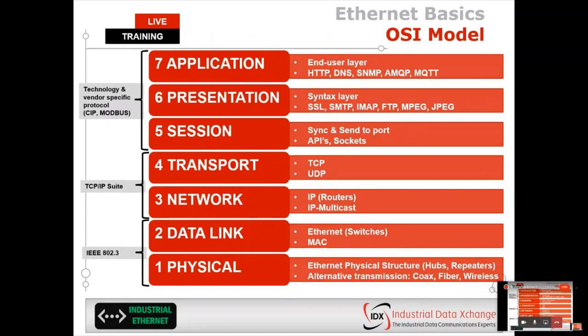This table in front of you is called an OSI model. An OSI model is used to describe a communication system - it can describe any communication system. For example, PROFIBUS doesn't use all layers; it only uses three: layer 1, 2, and 7. Layer 1 is the physical layer - we spoke about RS-485, your purple cable. Data link is the PROFIBUS protocol, or FDL, how devices communicate on a PROFIBUS network. Then your standard application layer defines why you're using this network - to transfer analog data, or start or stop a VSD, whatever it might be.